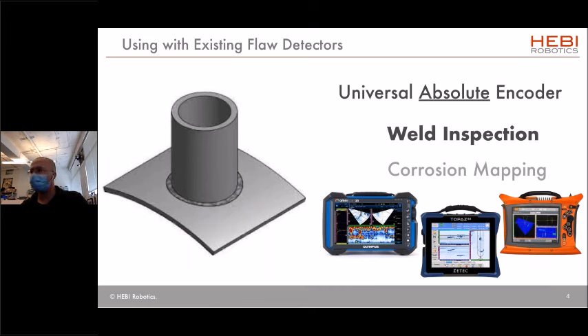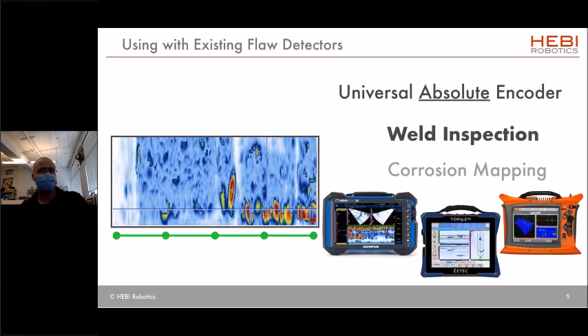So the modes that we'll demonstrate shortly are two applications. The first is weld inspection. Again, this would be something that you plug into any range of existing flaw detectors. The first thing you do is take the arm, and once you fix the base, you take the end of your probe, literally the probe that you're going to inspect with, and you touch different points around the weld that you want to inspect. Once you've done that, our software connects it with smooth curves, and we are then able to stretch that curve out into a straight line and have that become your B-scan.